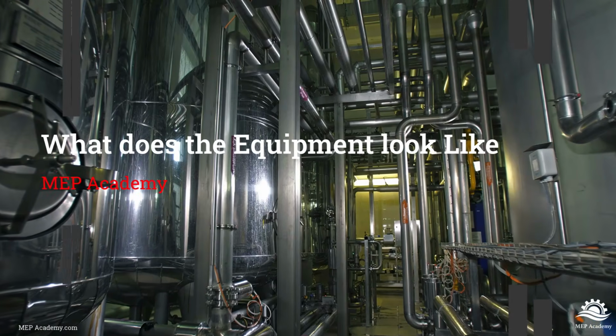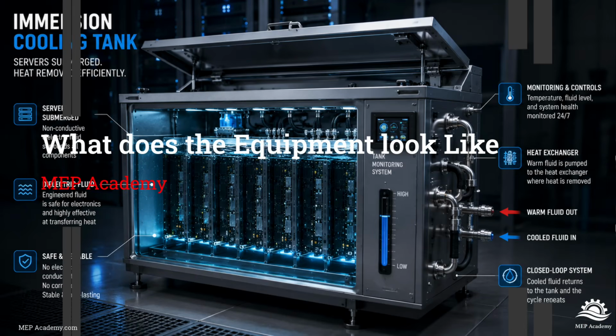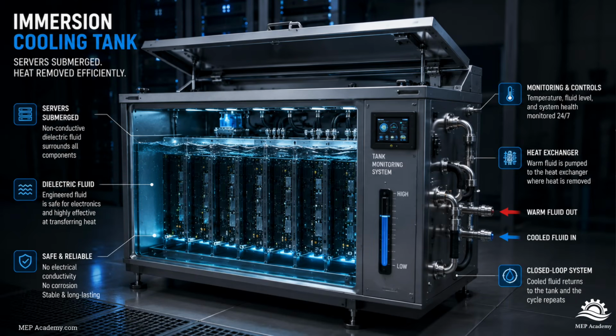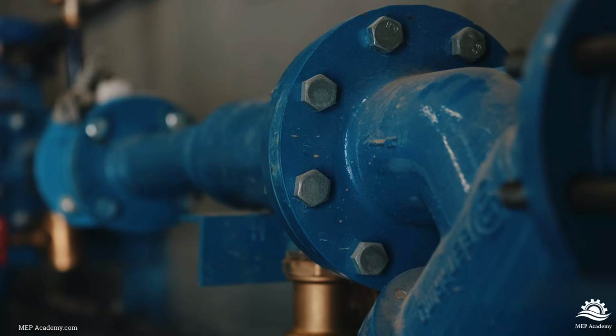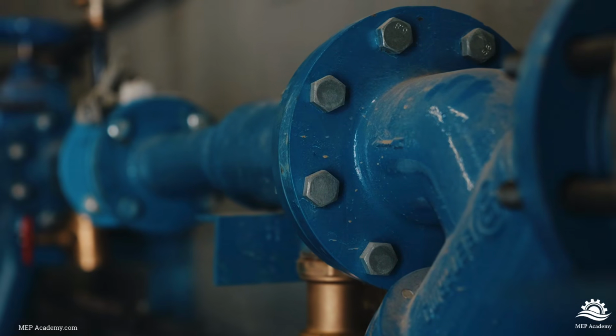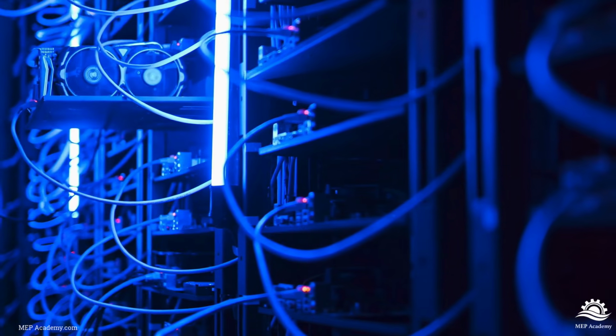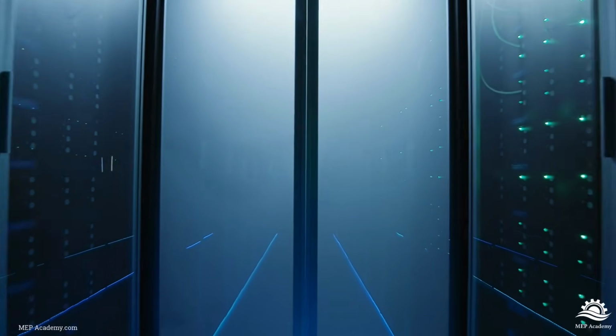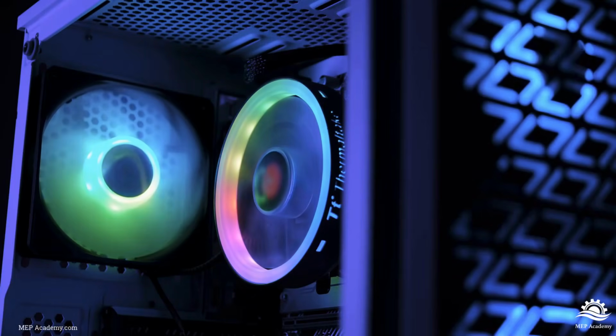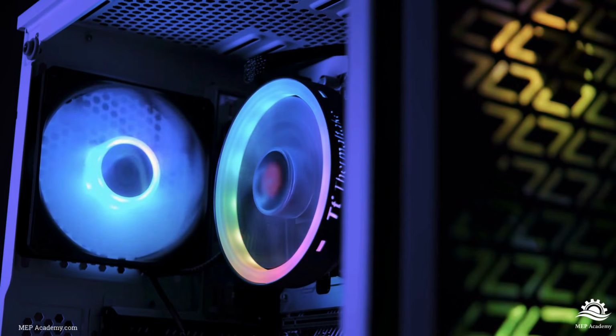So, what does the equipment look like? Imagine a large bathtub with a lid. Inside that tank are server blades mounted vertically. Technicians can open the lid and remove individual servers for maintenance. The tanks contain fluid distribution systems, heat exchangers, monitoring sensors, temperature controls, and connection points to the facility's water loop. Interestingly, because there are no server fans, the environment becomes dramatically quieter. One of the loudest components inside traditional servers simply disappears.